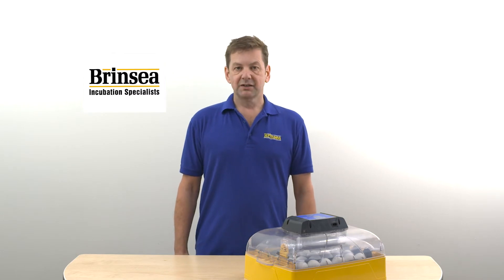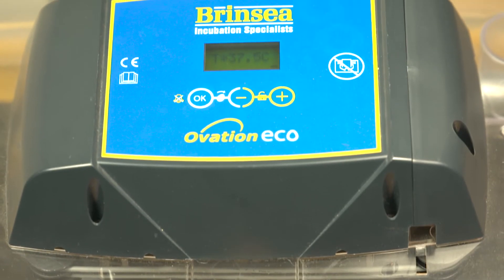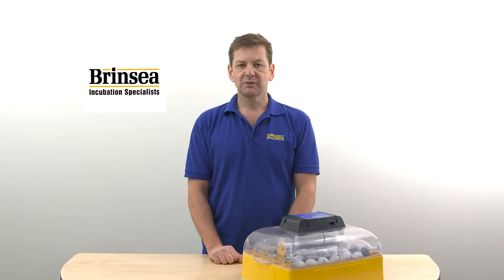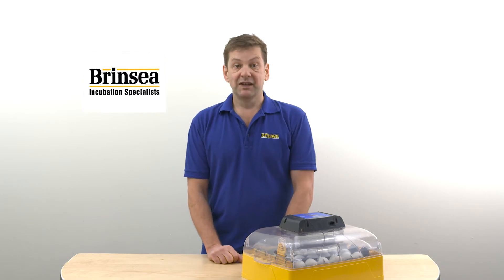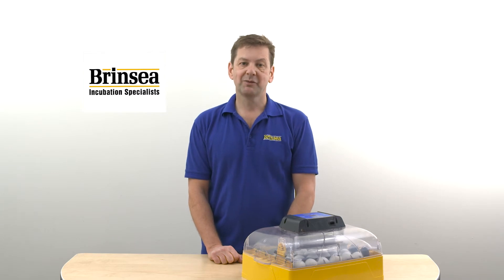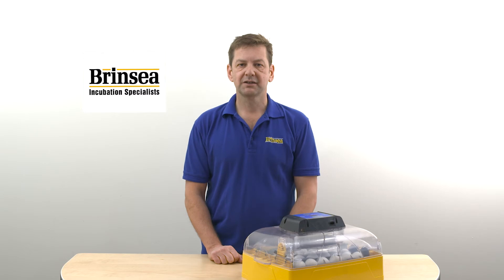All Brinsea incubators have a thermometer built into them, these days mostly digital displays of temperature. We do get customers often contacting us saying that they've put a second thermometer in and they're getting a different reading, and this is causing problems and they want to recalibrate. The main point of this video is to say that the Brinsea incubator thermometer is the one to trust and go by, but I want to explain why that's important.